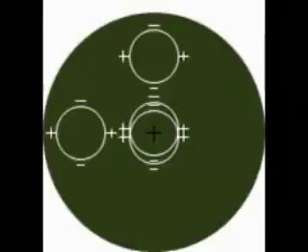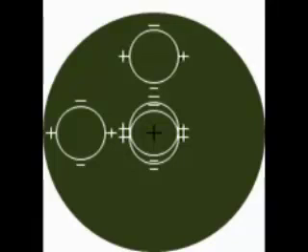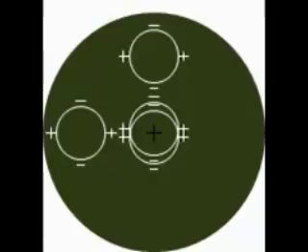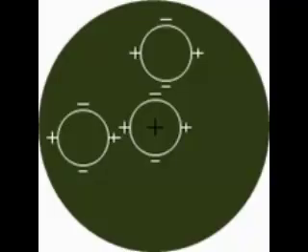Looking through the eyepiece, you will see the target mires. Note, the target mires may be blurred. If the target mires are blurred, turn the focusing knob to clear the image. The black plus sign should be in the center of the bottom right-hand circle. This is also known as our focusing circle. Turn the elevation knob if the plus sign is not in the center. Once the plus sign is in the center of the focusing circle, the optical axis of the instrument will coincide with the patient's visual axis.